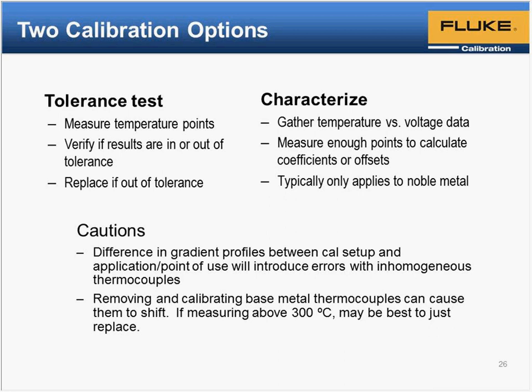Generally, most people are tolerance testing thermocouples, especially base metal. This is where you pick some measurement points and check the thermocouple against its specified accuracy, and you either reject or accept it based on whether it's in tolerance or out of tolerance. Then there's the method some use, especially with noble metal thermocouples, where we do a lot of characterizations. This is where you gather enough temperature versus voltage data that you can calculate a new thermocouple curve or new coefficients, or you may just calculate offsets and report them to your customer, so the customer can then apply offsets to compensate for the errors that you see during calibration.